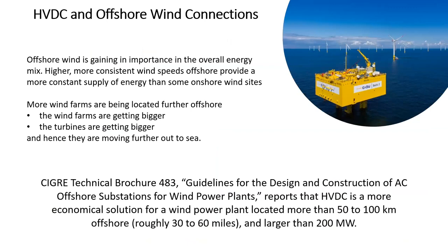This slide demonstrates one of the technical benefits and shows how HVDC technology has already been recognized within industry for playing a vital role in connecting renewable offshore power with an inland grid. And what I was saying earlier about the break-even point, you can see at the bottom. If the wind park is located more than 50 to 100 kilometers, so 50 to 100 is a range, at sea from land and has a generation larger than 200 megawatt, then HVDC is likely to be the more economical solution than HVAC.